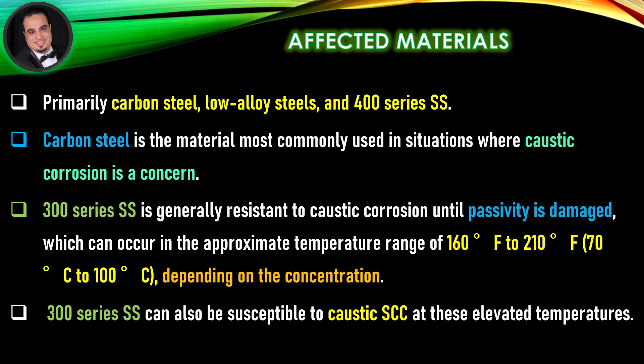Affected materials: Primarily carbon steel, low alloy steels, and 400 series stainless steel. Carbon steel is the material most commonly used in situations where caustic corrosion is a concern. 300 series stainless steel is generally resistant to caustic corrosion until passivity is damaged, which can occur in the approximate temperature range of 160°F to 210°F depending on concentration. 300 series stainless steel can also be susceptible to caustic stress corrosion cracking at these elevated temperatures.